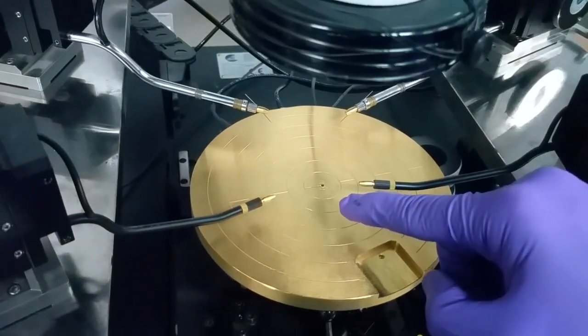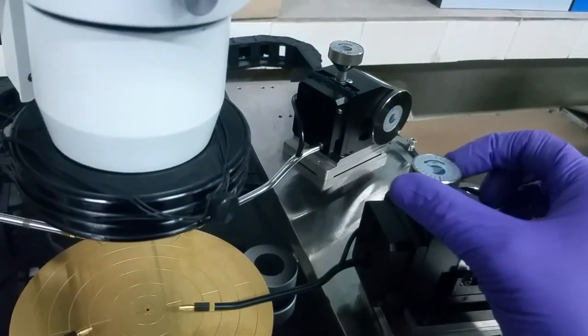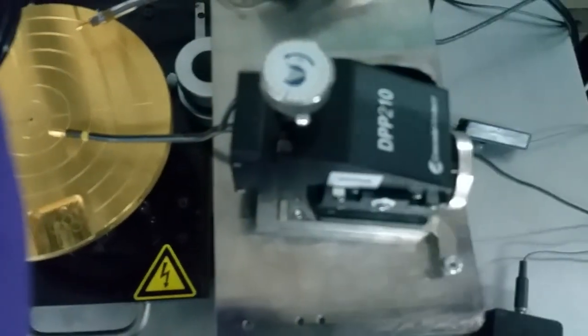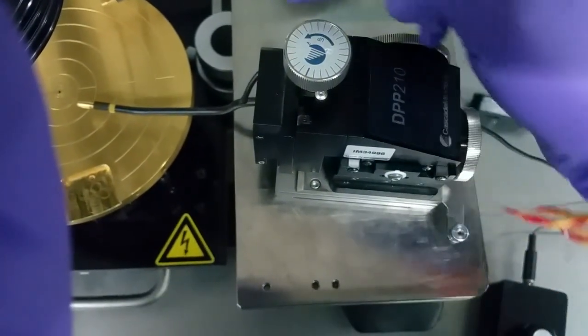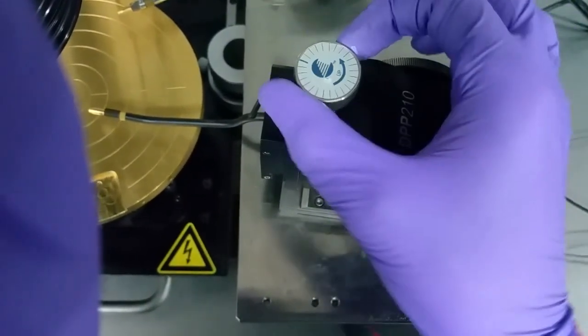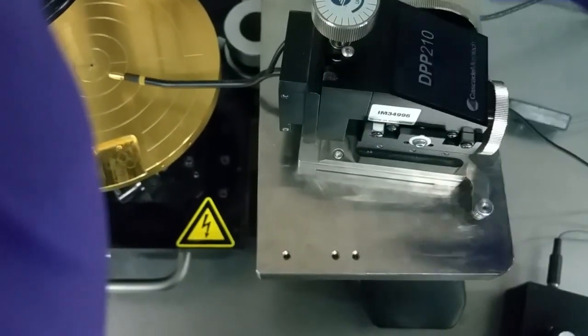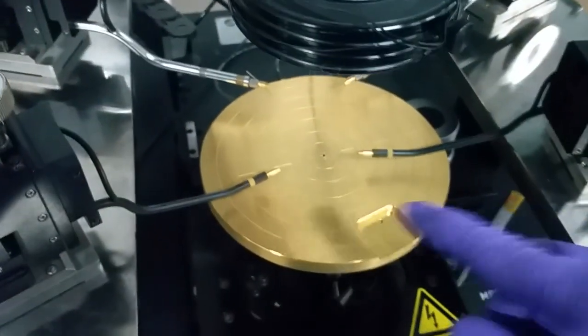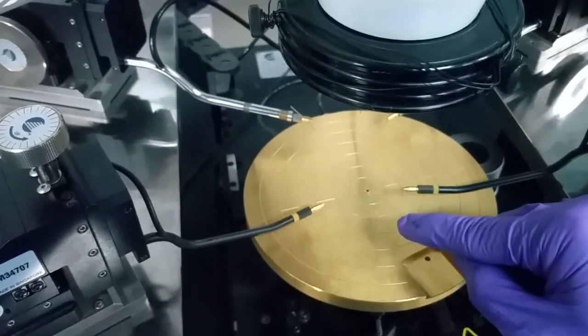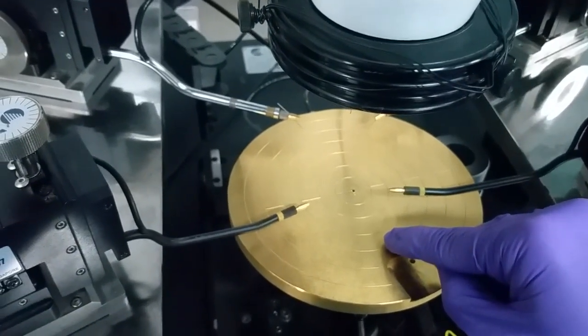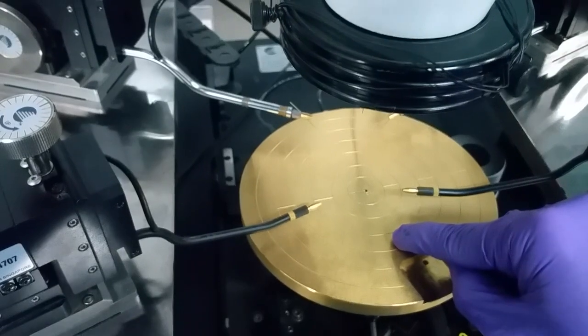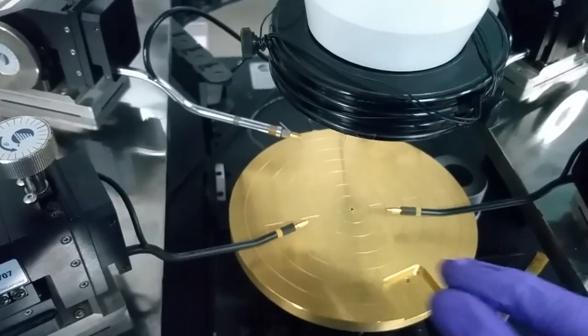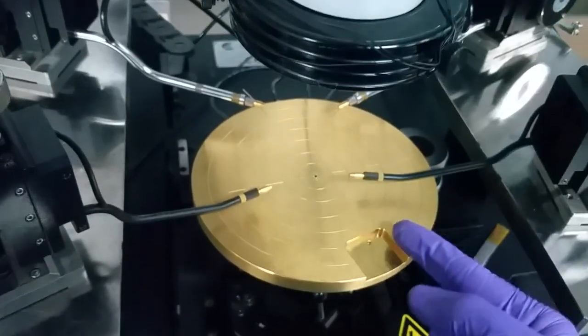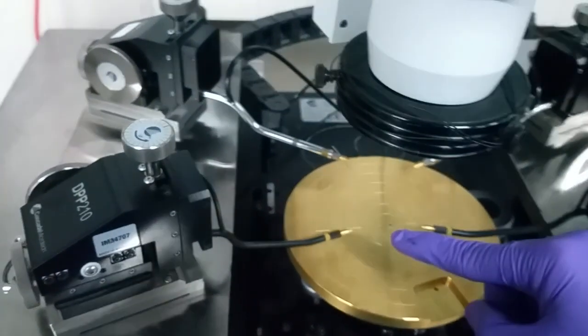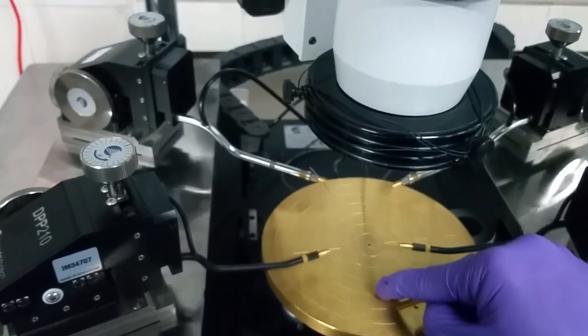So you have to carefully and slowly move down the Z from this knob, this one. Here it is mentioned that in this direction it is up, so it goes up in this direction and goes down in this direction. Similar is the case for X and Y. It is mentioned here which direction to go. Then when you are moving the probe down, it will meet the shadow, and when it touches the sample, you have to move slowly and just slightly push it to make sure that it is connected. You should not push it too hard or too much, otherwise the probe tip may get damaged or your sample may get damaged. So slowly move the probe down. When it is connected to the sample, stop there. Okay, now your connections are made.